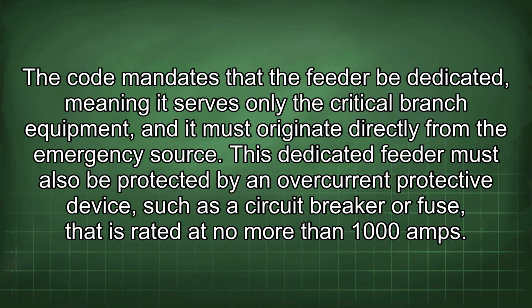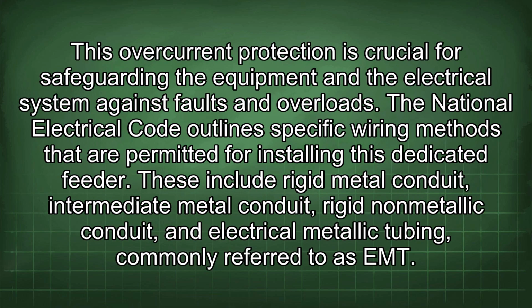This dedicated feeder must also be protected by an overcurrent protective device, such as a circuit breaker or fuse that is rated at no more than 1000 amps. This overcurrent protection is crucial for safeguarding the equipment and the electrical system against faults and overloads.